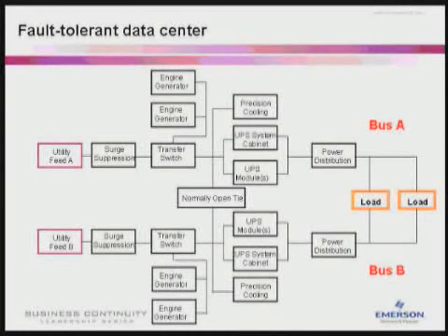Static switches are not shown on this one line. They would be between bus A and bus B to power single-corded loads. We're also seeing static switches used for fault isolation as well as feeding dual-corded loads on multiple bus systems.